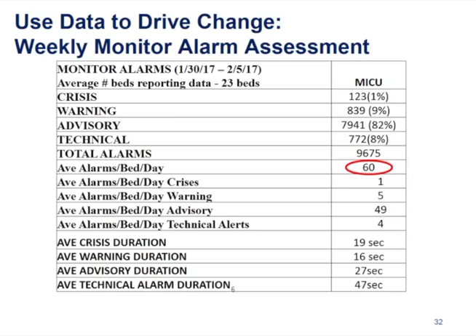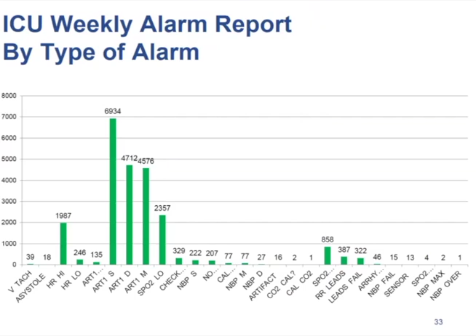In addition, the data is further broken down on our report to show exactly what's alarming on that unit. So it can easily be seen that the arterial line systolic, diastolic, and mean alarm limit breaches are the predominant reason for monitors alarming in the MICU. So to reduce alarm burden, it would make sense to target alarm interventions towards those 3 things.